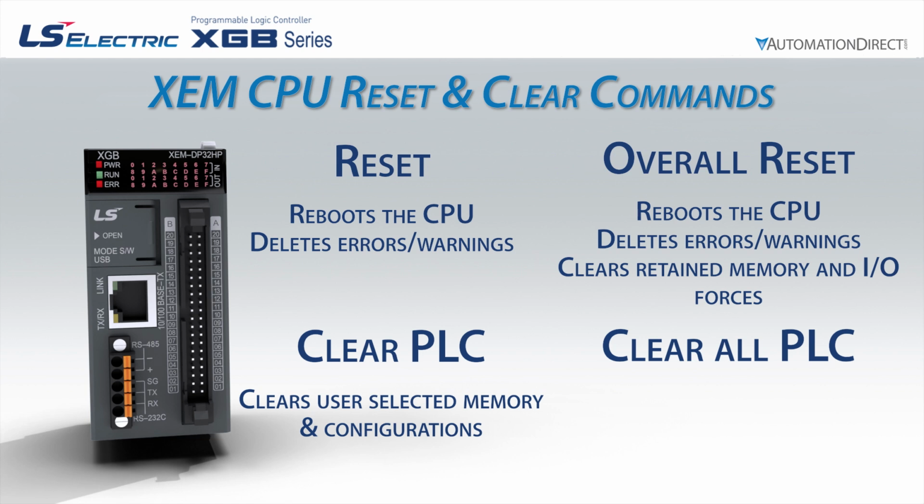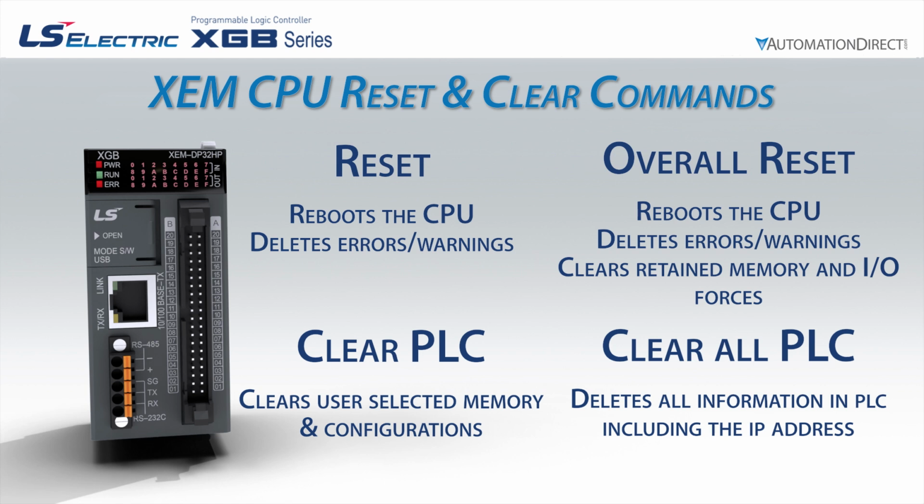The clear all PLC command will empty out the entire CPU of any stored information, including the CPU IP address. It clears out all programs, memory, forces, configurations, communication, comments, etc. This should be the very last step taken for resetting a PLC, and will usually only be used when a CPU needs to be repurposed for an entirely new project from the ground up.